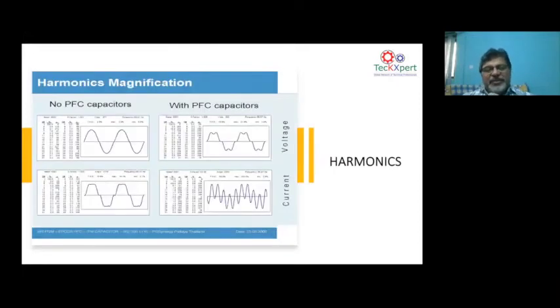Go to the next slide. Now you can simply see this slide. It's a quick slide. When there is no power factor correction, your waveform looks fine. When there is power factor correction, it produces harmonics and distorts the waveform. You can see the voltage waveform distorted and the current waveform distorted, because plain capacitors are installed in the network.